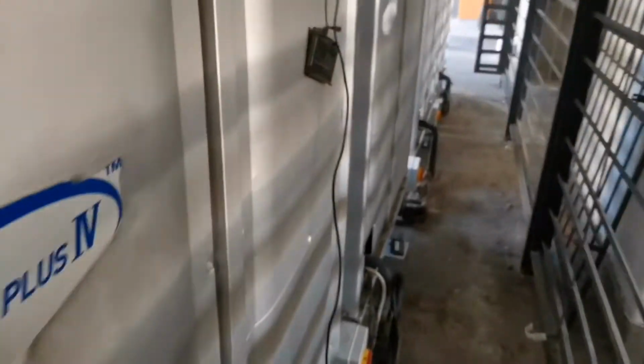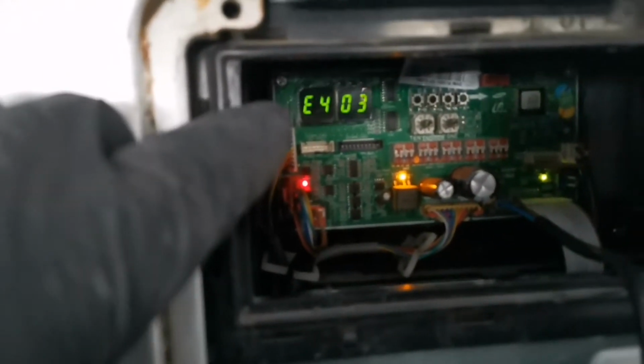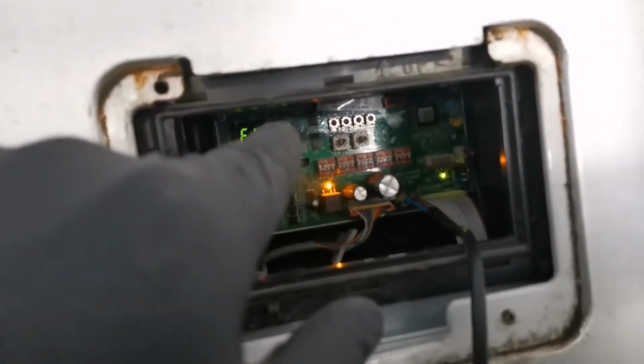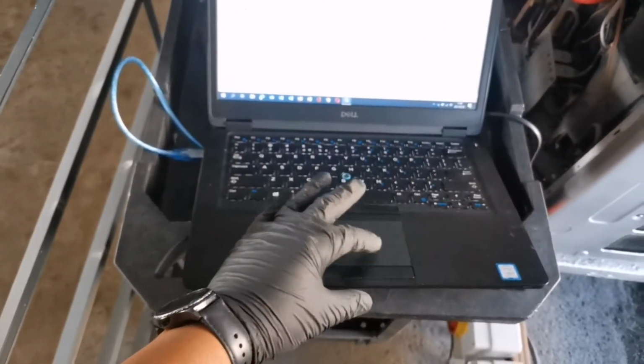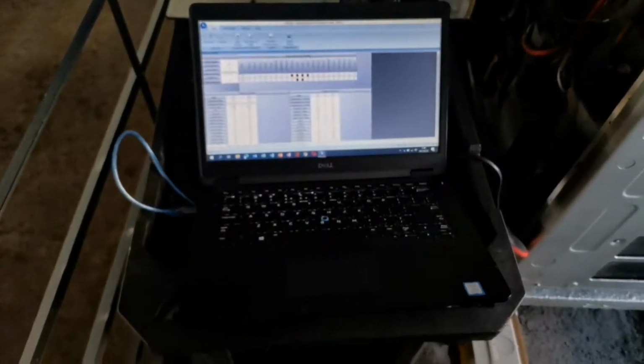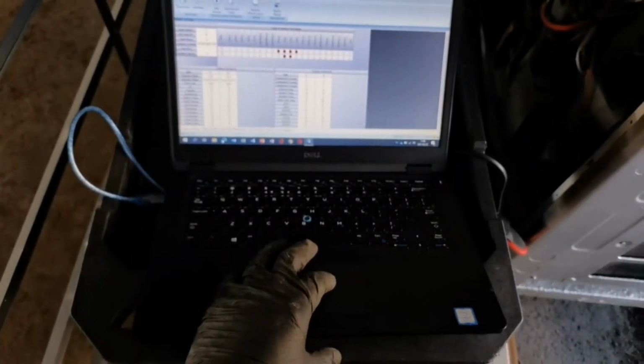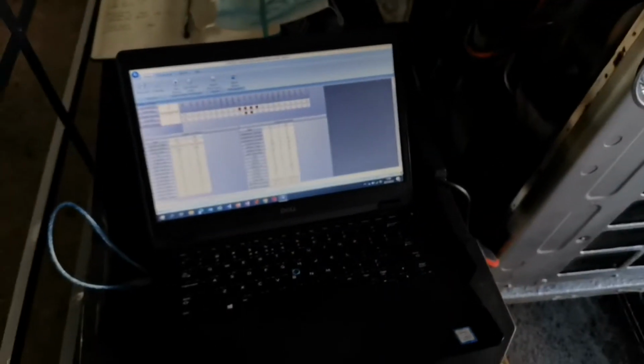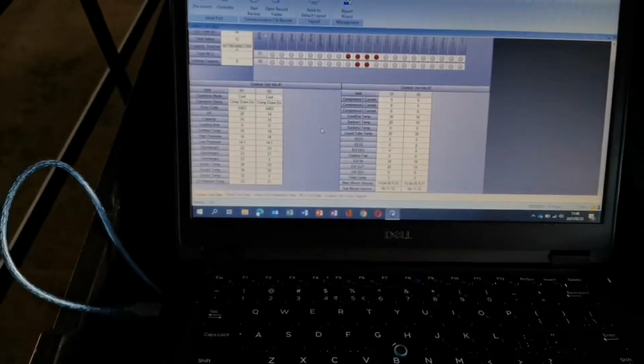So now we are checking out this system right here, which has got an E403 on U200. U200 means it's the main outdoor. If it was U201, it would mean the slave condenser. So on this system we got a 403. 403 is a freeze check alarm. Now we're in the middle of summer, and for the unit to give us a freeze alarm on the outdoor seems a little bit weird.